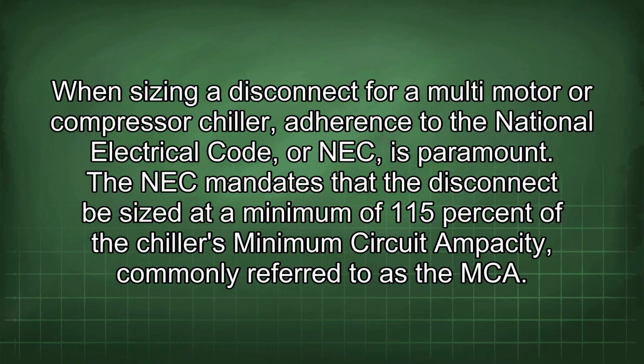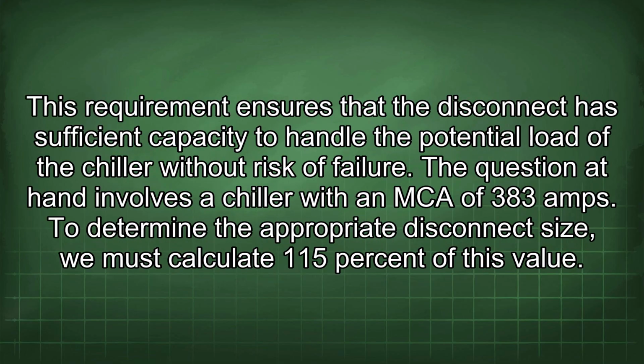When sizing a disconnect for a multi-motor or compressor chiller, adherence to the National Electrical Code, or NEC, is paramount. The NEC mandates that the disconnect be sized at a minimum of 115% of the chiller's Minimum Circuit Ampacity, commonly referred to as the MCA. This requirement ensures that the disconnect has sufficient capacity to handle the potential load of the chiller without risk of failure. The question at hand involves a chiller with an MCA of 383 amps.